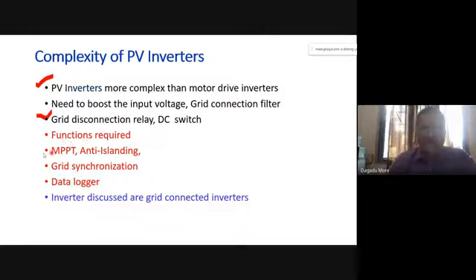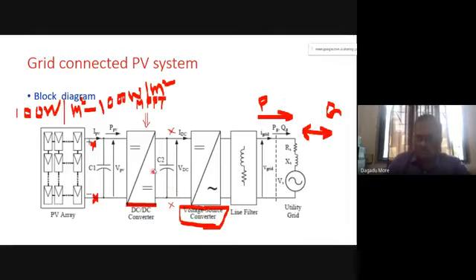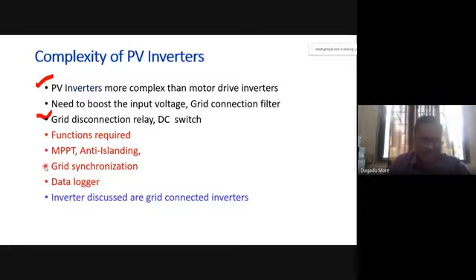Also, what is important, as we have discussed, is that our panel should operate at MPPT, so we extract the possible maximum power from the solar panel. This is islanding: our solar system should become separate when the grid fails. That is, anti-islanding techniques we have to use. Then we require grid synchronization. When power resumes, automatically our solar system should be connected to the grid, and for that we require a grid synchronization system. The solar system should connect automatically to the grid when power resumes. That is our grid synchronization.